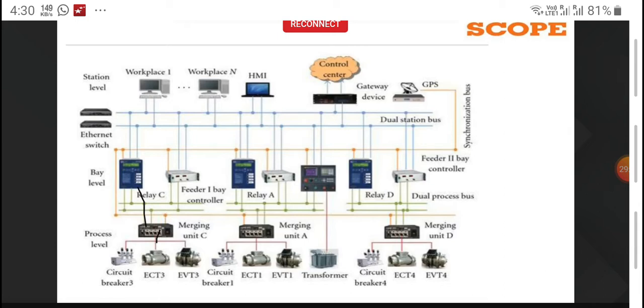Today the hybrid relays or numerical relays also have the option of adding this 9-2 protocol module to the existing relays, even though they are taking analog signals from the CT and PT. In future, if you want to change from the analog CT and PT to the electronic or optical CT and PT, without changing the relays you can just add the modules, the optical CT module and optical PT module, and still use those relays. Then again, from the relays to the substation SCADA system and to the LDC or SLDC.